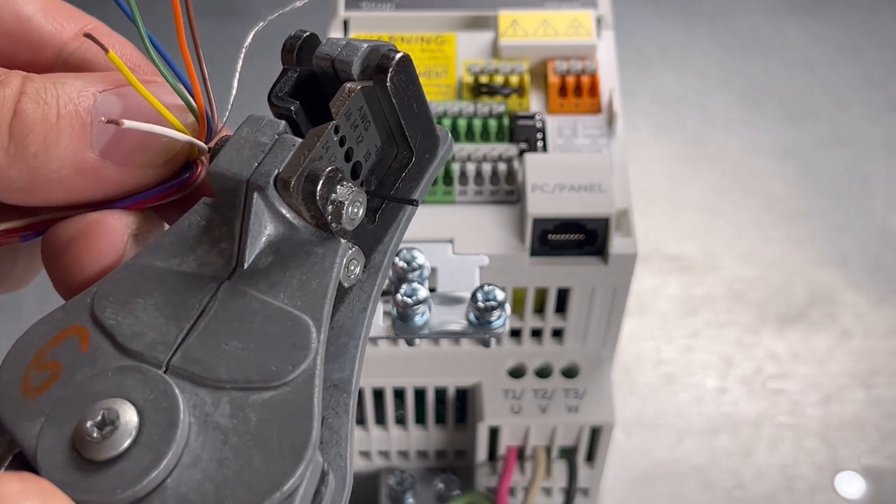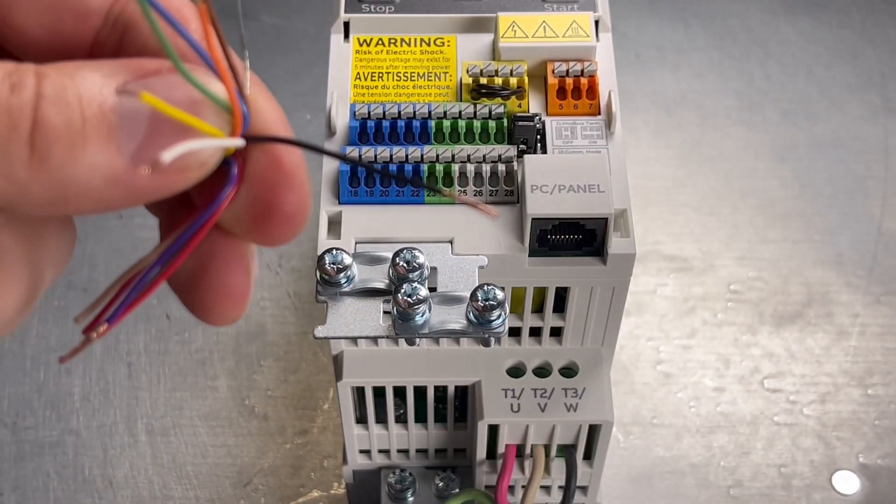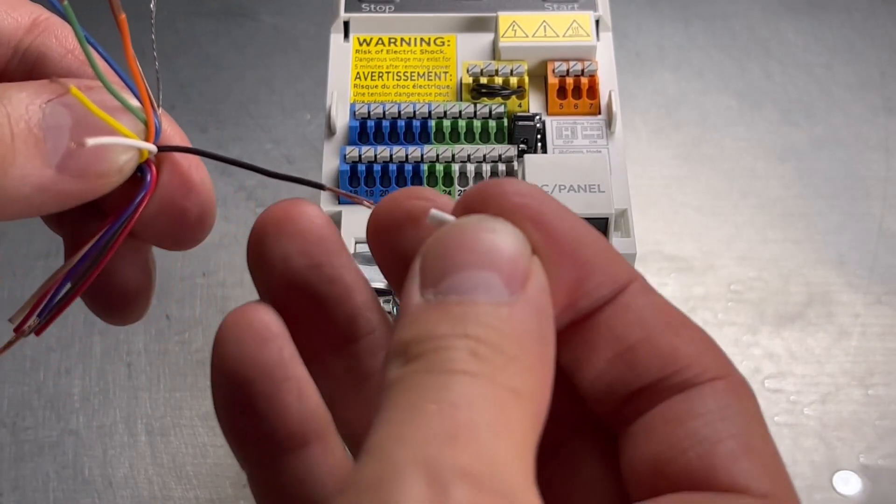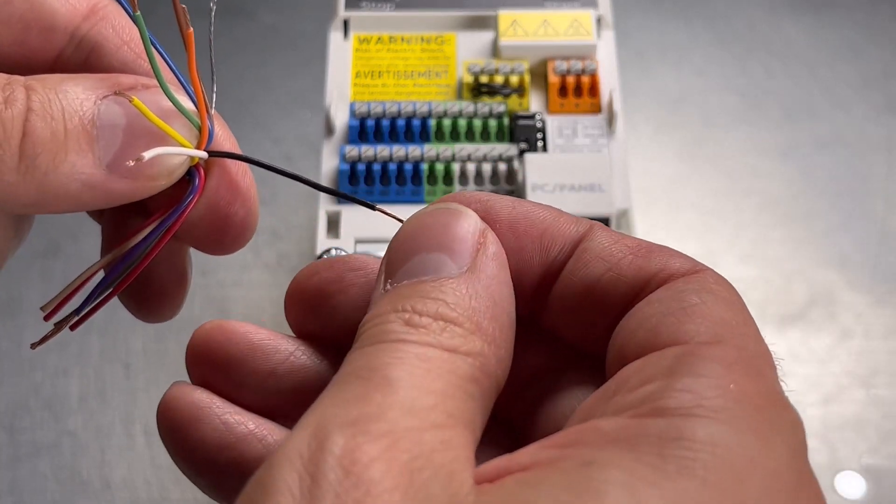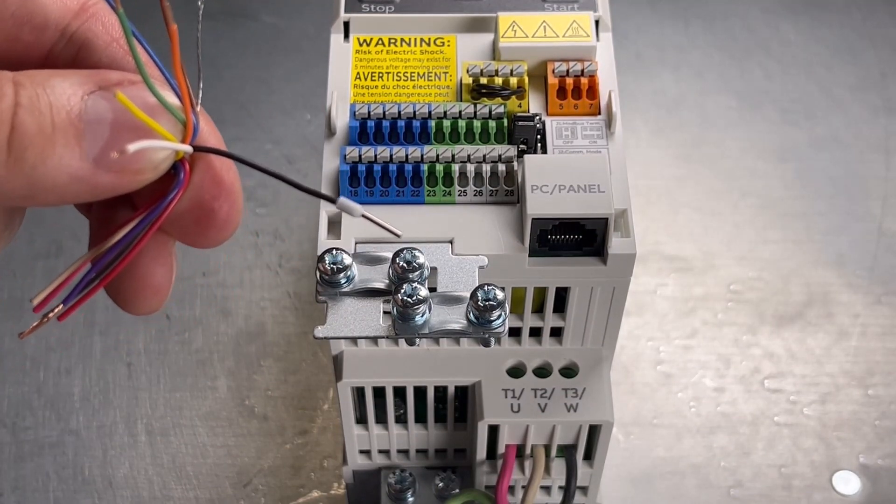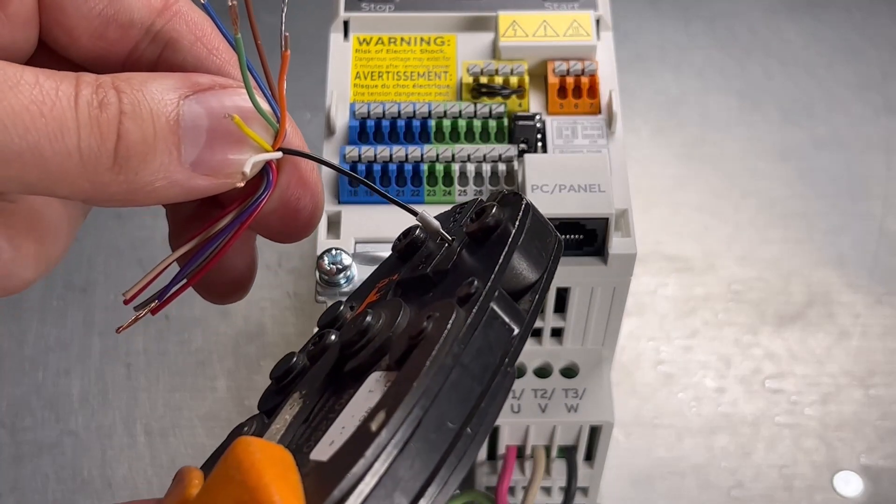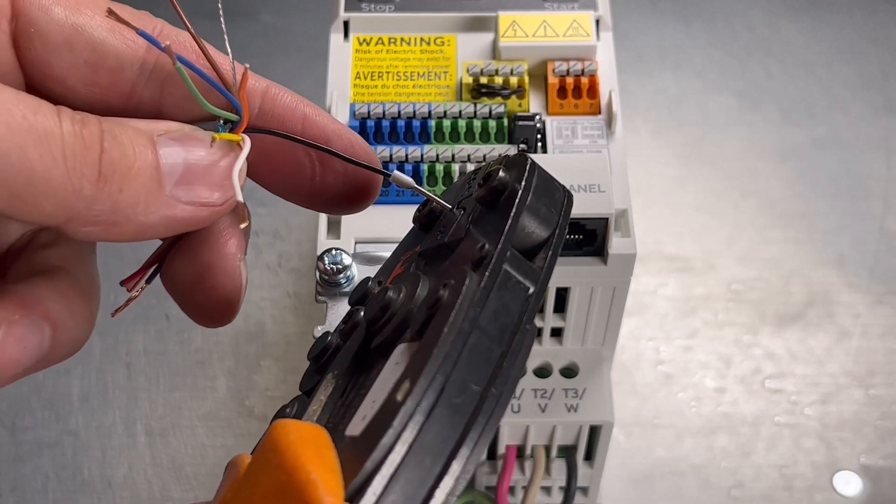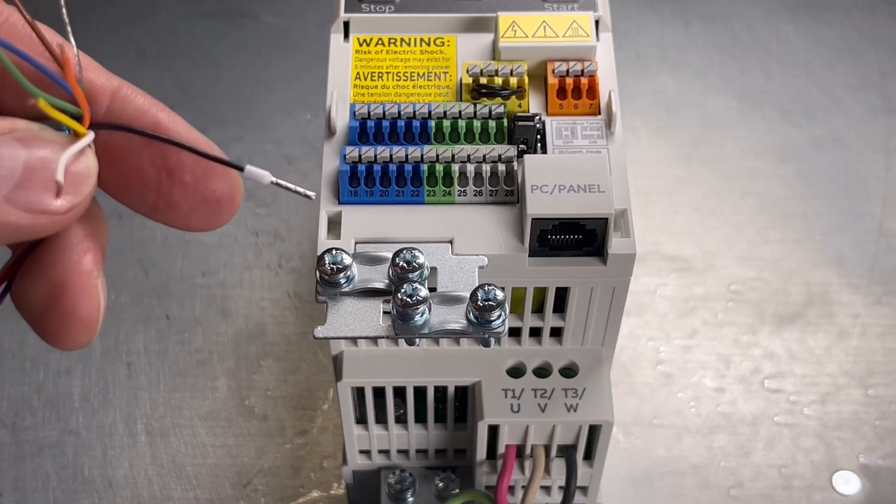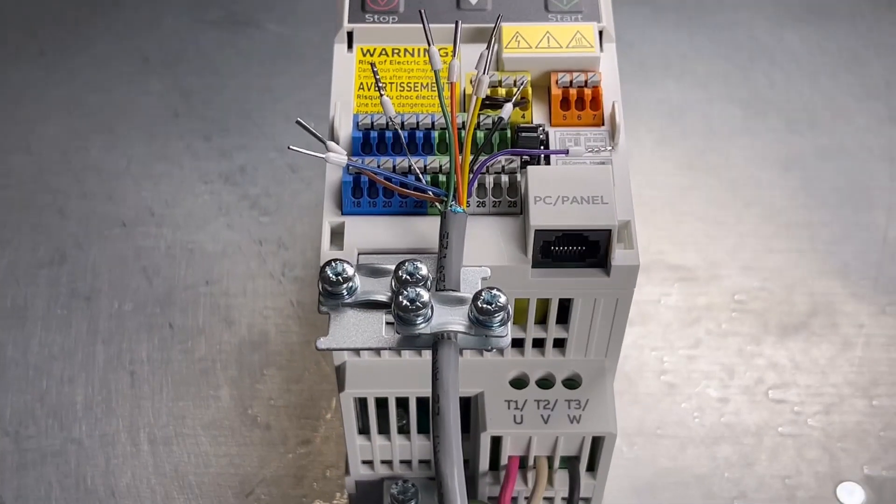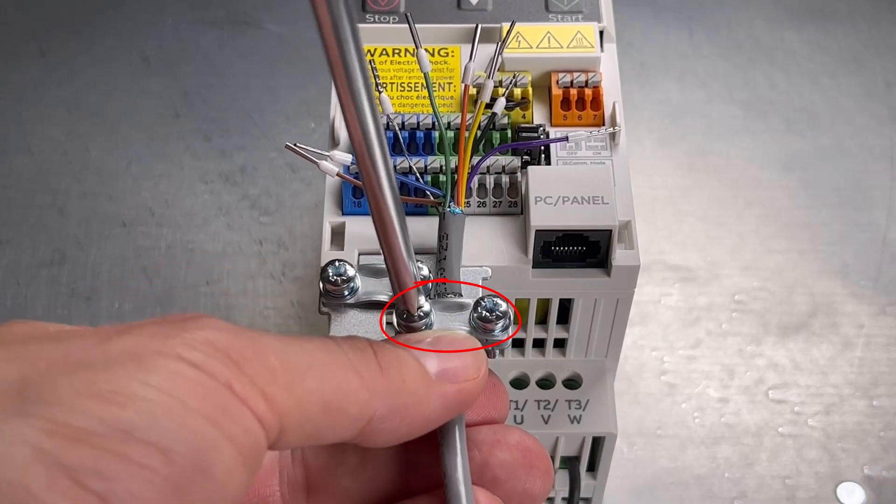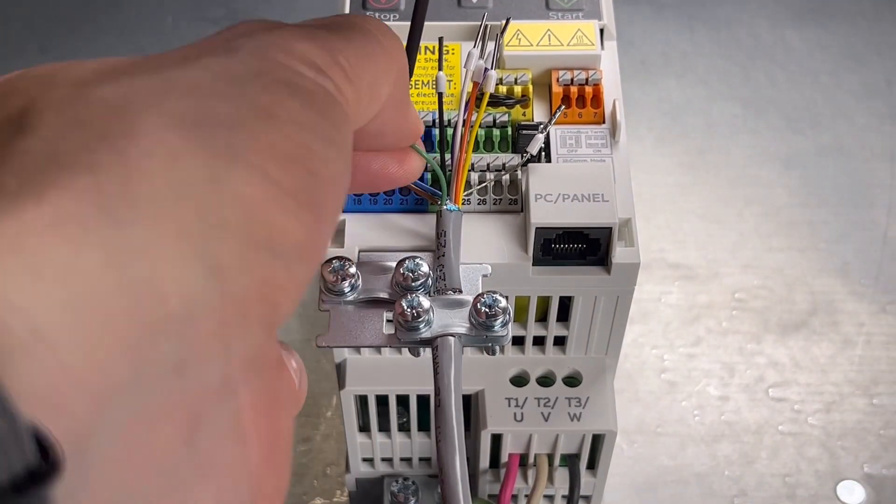Strip the ends of the control cable conductors. For stranded or multi-wire conductors, install ferrules at the bare conductor ends. Strip a part of the outer shield of the control cable. Use a 360-degree grounding clamp to connect the cable to the grounding tab. Connect the conductors to the correct control terminals.